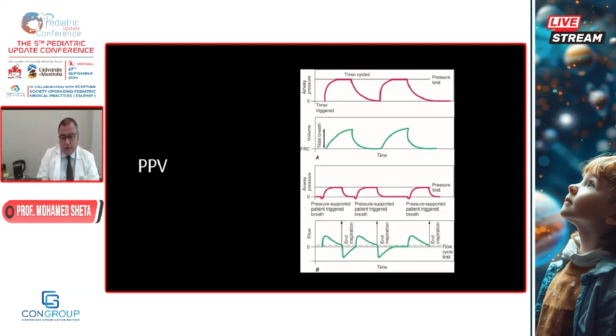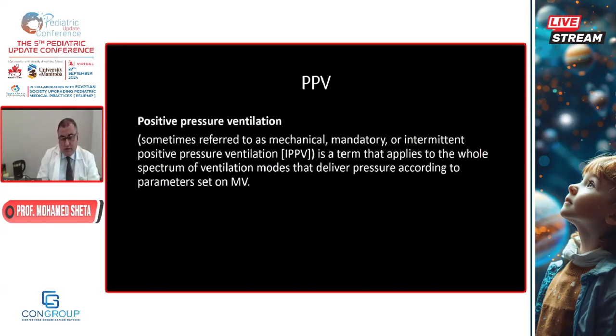The volume increases when the pressure increases, and vice versa, and also the flow. So, positive pressure ventilation is sometimes referred to as mechanical mandatory or intermittent positive pressure ventilation, and we'll see the modes and the differences. Now, continuous mandatory ventilation is very old and is not used now, except possibly during resuscitation, when you give continuous mandatory ventilation either by T-piece or by the ventilation built into resuscitation or warmer machines. There are some machines, especially from Dräger, that have built-in ventilation. This one is continuous mandatory ventilation.